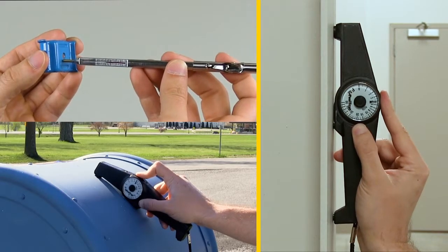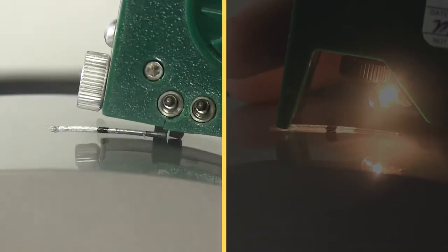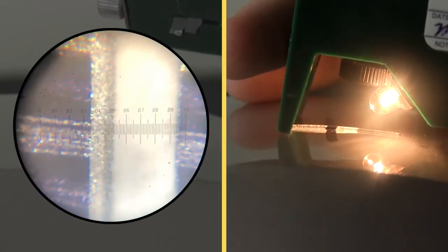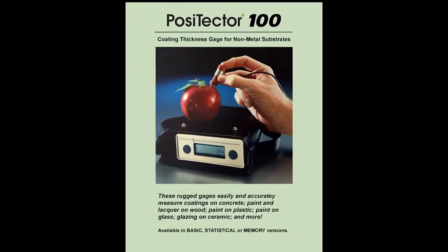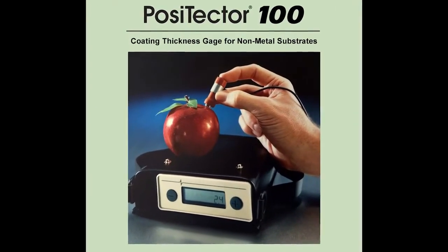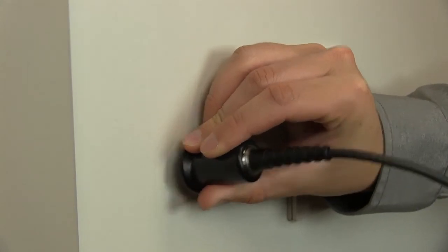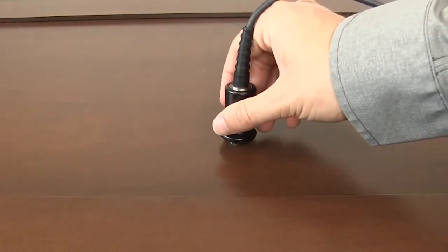For decades, measuring coating thickness on metals has been possible due to their magnetic and electrical properties, but measuring coating thickness on non-metals was limited to destructive methods. Everything changed in the 1990s when DeFelsko introduced the PosiTector 100. For the first time, it was possible to measure coating thickness over a range of substrates using a novel method: ultrasound.